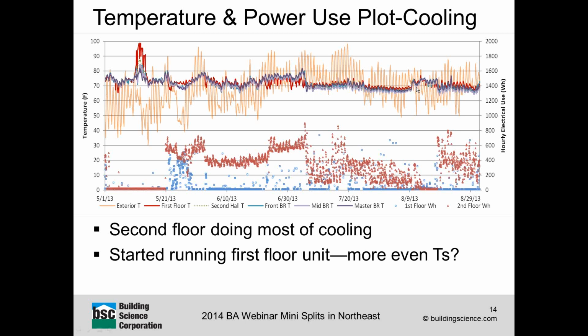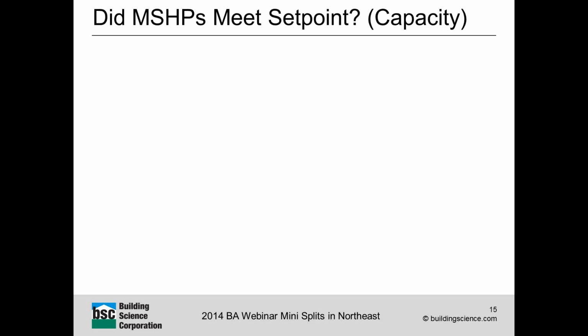So one of the questions you'll often face is, people do not trust heat pumps in a cold climate to heat a house. So let's look at equipment capacity. Did it actually meet set points and not have any comfort complaints on that front? So, like we said, we're using these heat pumps as a single source of heating in Massachusetts Zone 5A. Those two sites had design temperatures of plus or minus 2 Fahrenheit.